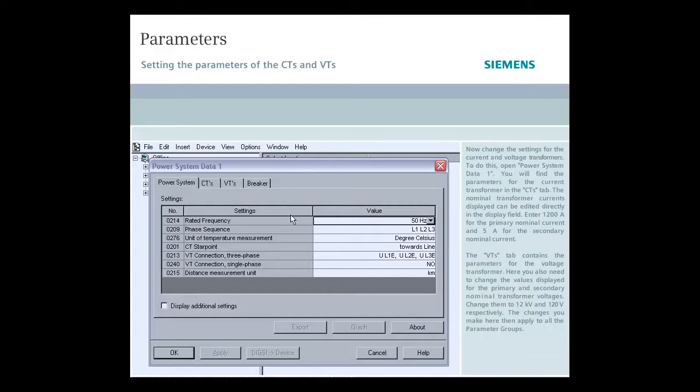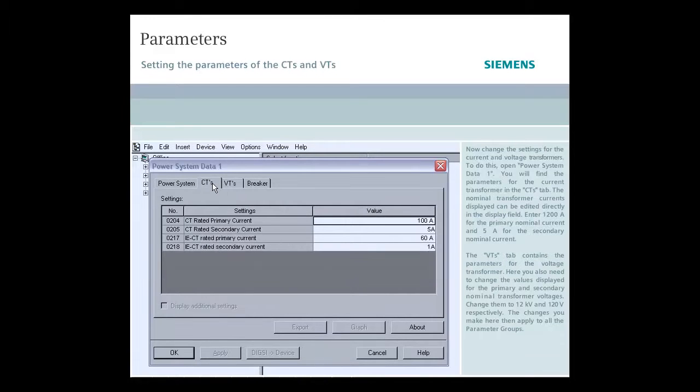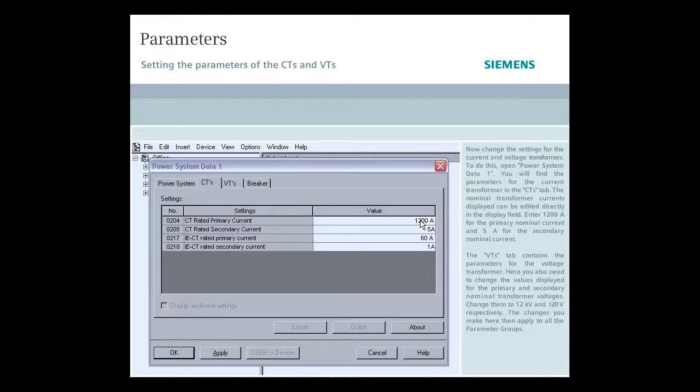You will find the parameters for the current transformer in the CTs tab. The nominal transformer currents displayed can be edited directly in the display field. Enter 1200 amperes for the primary nominal current and 5 amperes for the secondary nominal current.